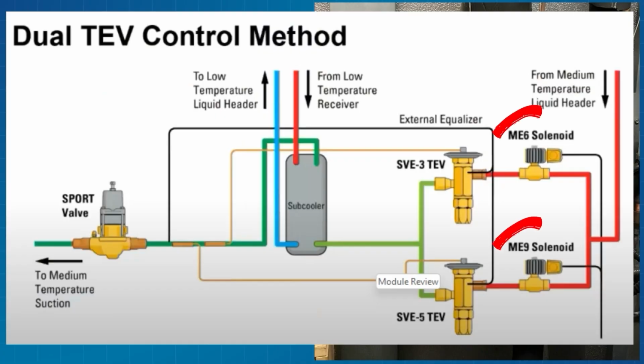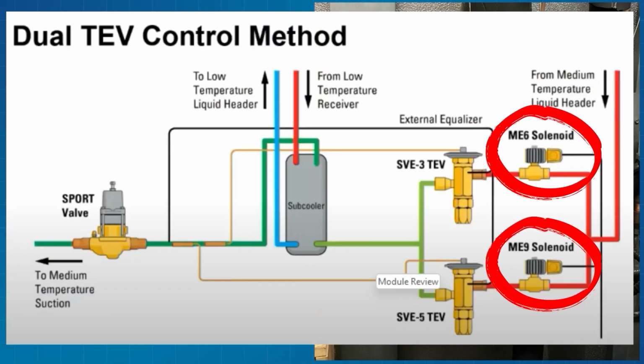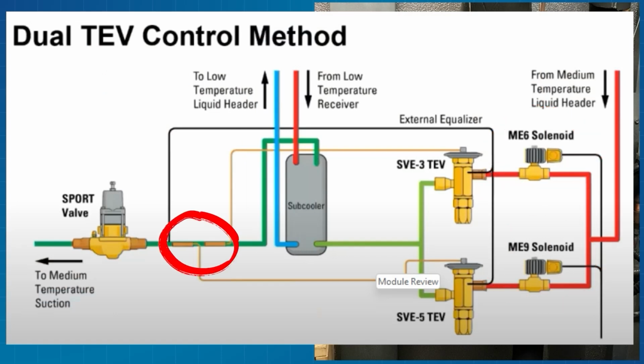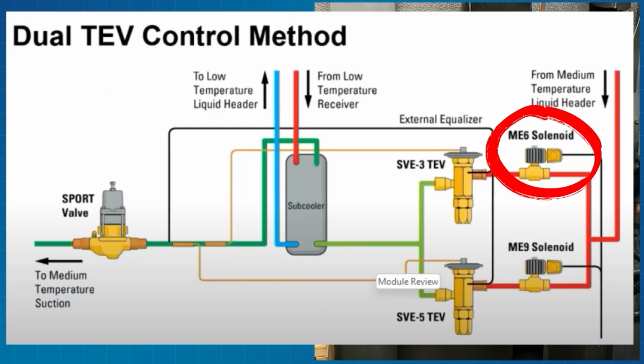Now, when we go to set these valves, that also requires we set these valves a little differently. We're going to start by turning off both of these solenoids. We're going to starve the evaporator completely. Then we're going to set up our superheat reading here, and we're not going to hit the min-max buttons and walk away. We're going to open one solenoid, just one, feed our case, and watch that superheat. And when that superheat hits 0, we know we flooded, we're going to shut it off and start over. But we're going to turn in our valve, and then do it again.